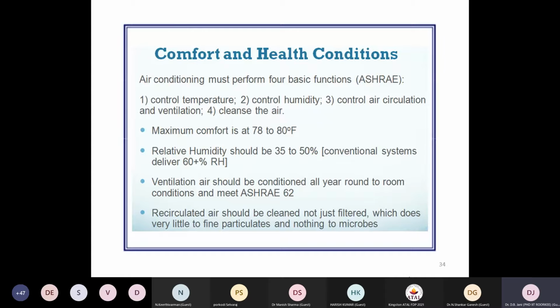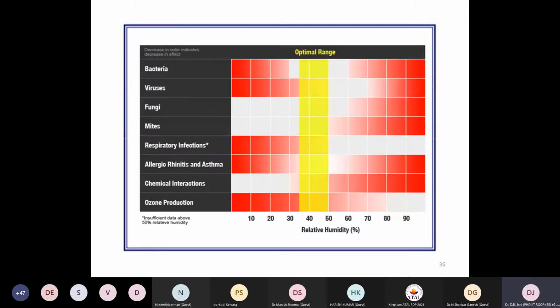So now the problem is to change the system. One thing to bear in mind is why the humidity is typically required in the range of 40 to 50. Nowadays, you may also see this in this corona age. For some part of the year, you find corona spreading in a greater way. Obviously lockdown and other things put some control over it, but ambient conditions and changes in humidity also play a great role. This graph was produced by eminent scientists based on a combination of medical and HVAC experiments, and the data is published in well-known journals.